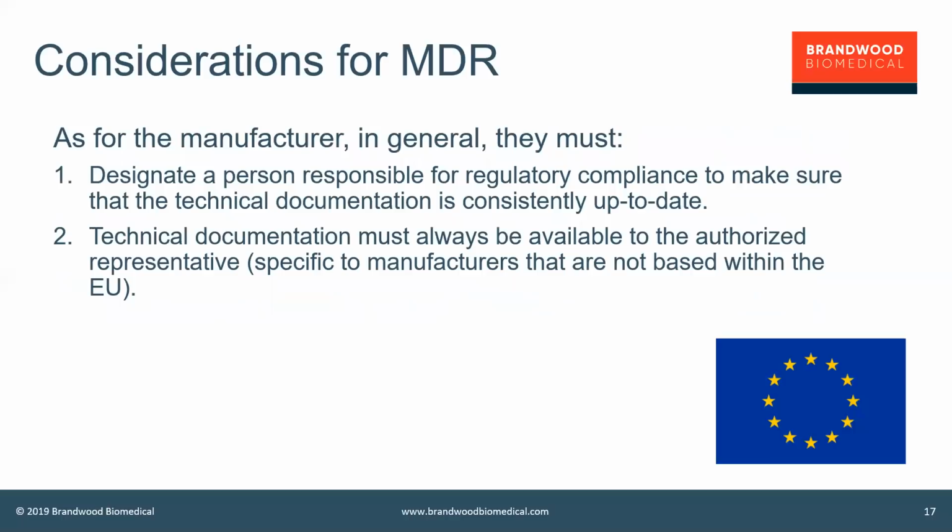There are a couple of just general manufacturing considerations that we need to make as well. Much like you would for ISO 13485 in designating a responsible party for your quality management system, you need to do the same as it comes to your regulatory compliance. So effectively, there needs to be somebody who is responsible for that. Now, it could be a position, it could be a specific person, but you need to designate that person within your documentation to show that they are going to maintain compliance of your documentation and technical file.